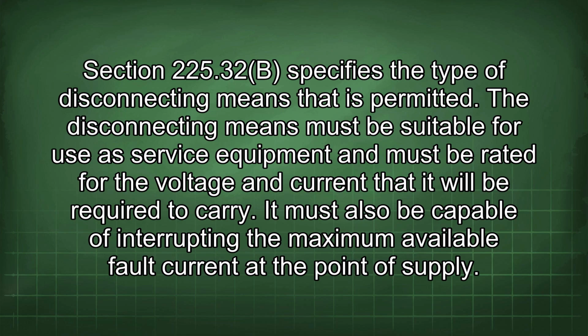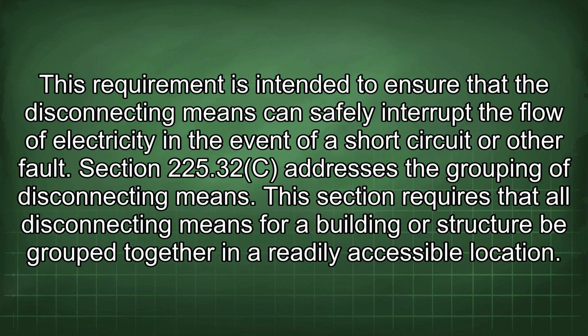Section 225.32b specifies the type of disconnecting means that is permitted. The disconnecting means must be suitable for use as service equipment and must be rated for the voltage and current that it will be required to carry. It must also be capable of interrupting the maximum available fault current at the point of supply. This requirement is intended to ensure that the disconnecting means can safely interrupt the flow of electricity in the event of a short circuit or other fault.